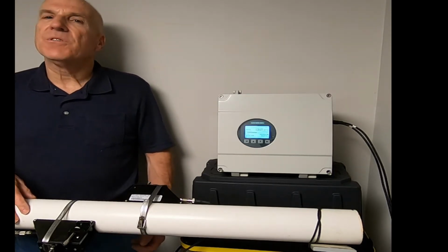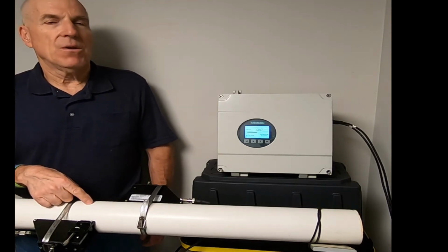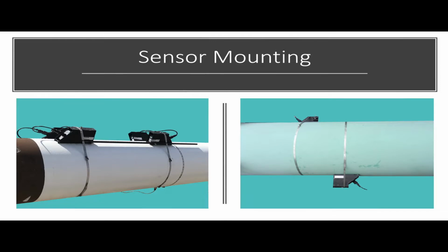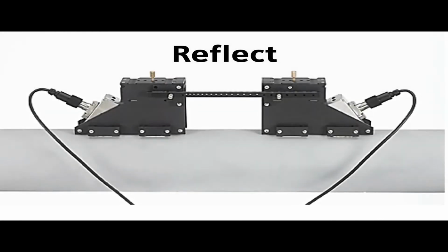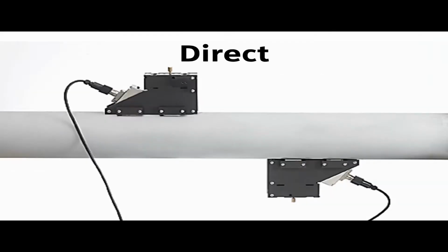In this video, I'm going to show you the simple way to install your flow sensors in direct mount, should you have to do so. As most of you know, there's more than one way to mount flow sensors. The most common methods for mounting are reflect, which is the preferred method in most cases. This is because reflect is the most precise mounting method, it provides the best accuracy, and it's by far the simplest. The alternative method is direct mount, which is the subject of this video. With direct mounting, one sensor is on each side of the pipe. Therefore, it's not possible to utilize a spacer bar, which makes the installation a little more tricky. But utilizing the procedures that I'll outline in this presentation, it will make it much more simple to accomplish.